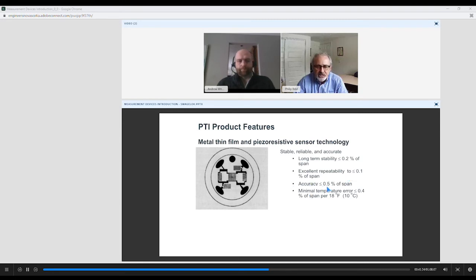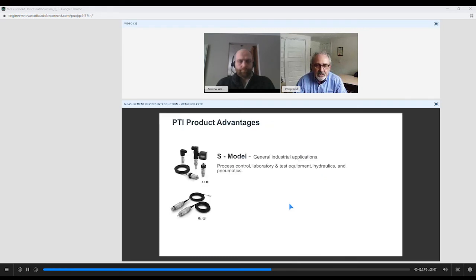Accuracy levels are at 0.5% of span or better, with minimal temperature errors. These are compensated for as well, as I mentioned, in that temperature compensating circuit. And one thing that pressure gauges don't like much is a lot of shock and impulse, so the diaphragms are much more resistant to that shock and impulse than in a gauge.